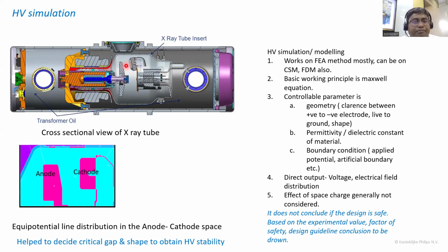Whereas people who are doing the optical part of the design, they need a smaller distance between these two. Why? Because as I say, X-ray will be produced from this metal surface, and if you have a big distance between these two, the electrons will scatter, will have a fanning effect more.